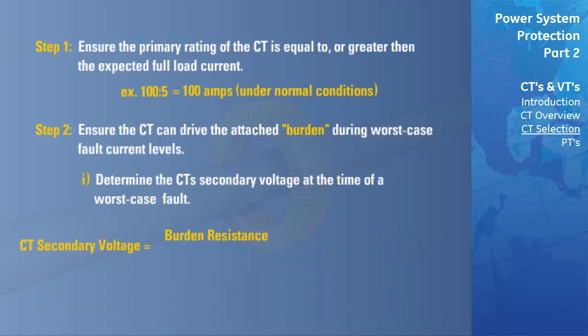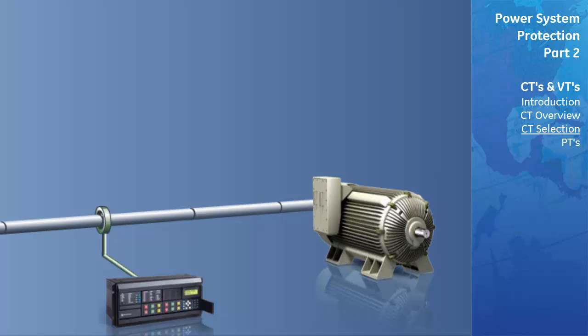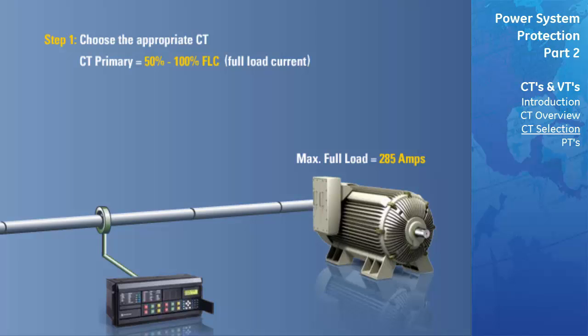Now we will look at a practical example. Let's assume we have a motor that draws a maximum full load current of 285 amps. The first step is to choose the appropriate CT. It is customary to select a CT with a primary rating falling between 50 to 100% of the maximum full load current — in this case 285 amps. Possible CTs for this use would be 300 to 5, 400 to 5, and 500 to 5 CTs, because the primary rating falls between 50 to 100%. We would select the CT closest to 100%, since the higher the CT ratio is over the full load current, the less sensitive that CT will be. Since accuracy is always imperative, we will select a CT with a 300 to 5 amp conversion, where the primary rating of 300 is closest to the 100% primary rating.